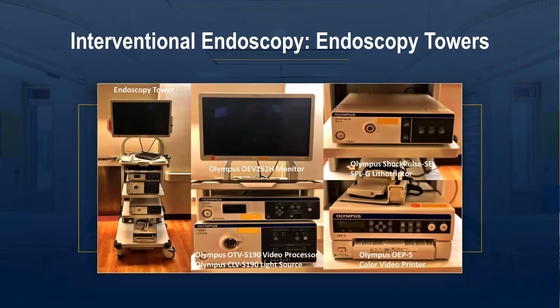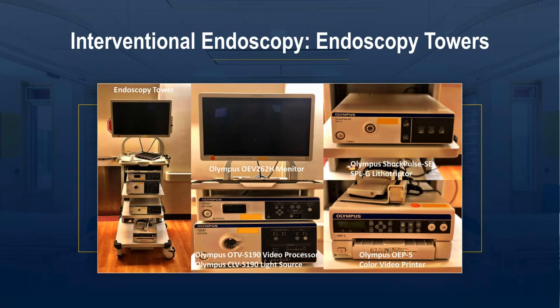Most of this equipment comes with towers that can be obtained from urologic or gastroenterology colleagues. The towers have a large monitor — including high-definition options — a host of video processing systems, and the ability to save images to a flash drive or the medical record. They also include power generators for cameras, light sources for the endoscopes, and generators for the lithotriptor devices for breaking up stones.